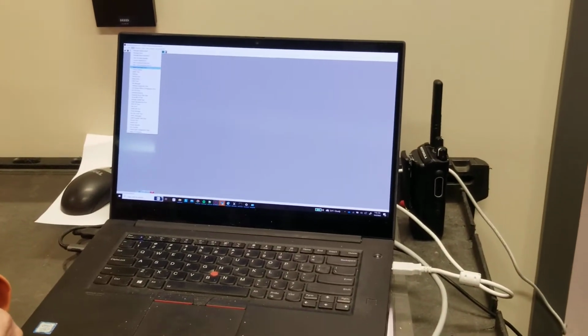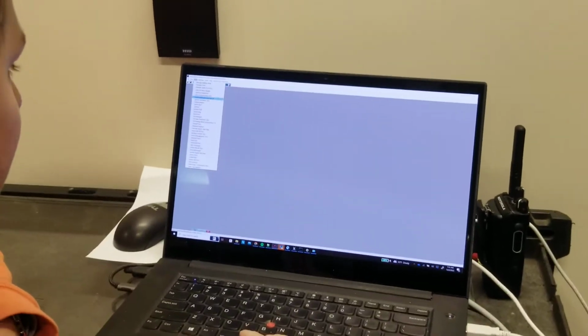Okay. 0 and 254 are usually reserved, for send and receive. So I usually go for 253 because generally they don't get up that high. For example, the one that I just connected to via USB was at 18. Even if you skipped a few, you have to get real high to get up to 253. Right.